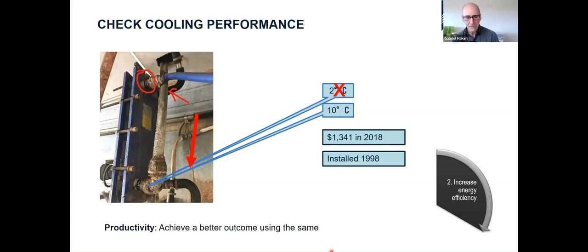The milk pump, the plate cooler pump, was still running, but it wasn't doing a very good job. In fact, the temperature difference was 10 degrees. By correcting it, we worked out that we would save around $1,350 a year based on those figures from a few years ago. That cooler had been installed 20 years earlier - imagine the money that's been lost, not working properly. So the simple fix is to reverse the flow direction, and make sure the water is as cold as possible.